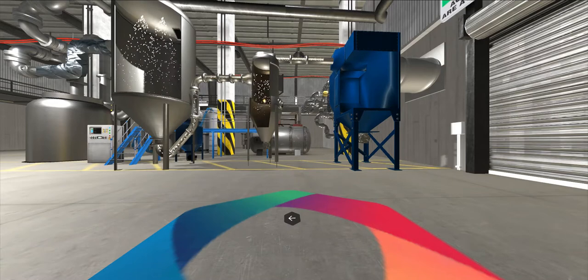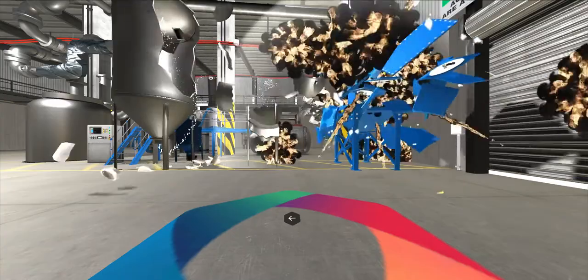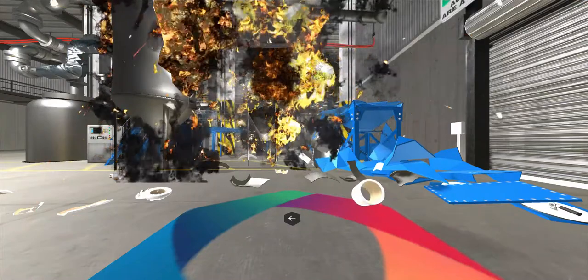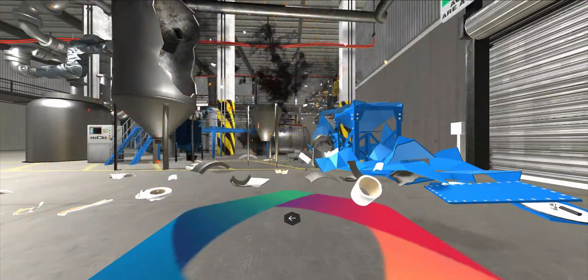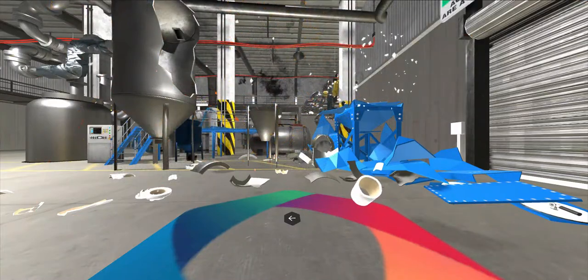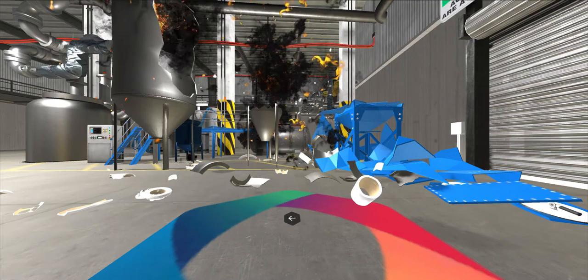That ember triggered the explosion. The pressure wave and flame front moved rapidly upstream to the interconnection. This propagation from the initial explosion disturbed dust in the plant, which created an even greater hazard. The resulting secondary explosion can be even more devastating than the initial event.